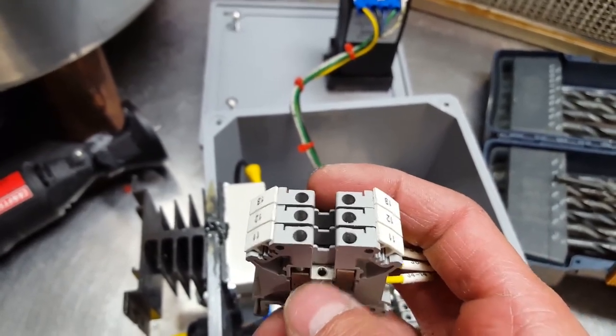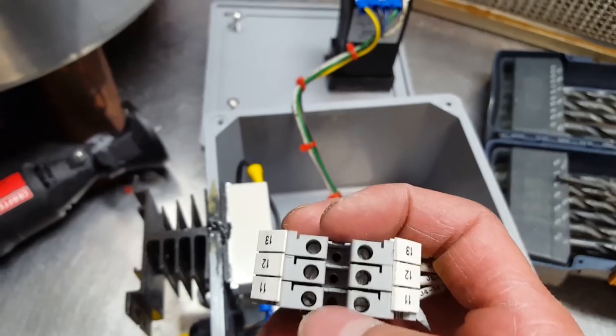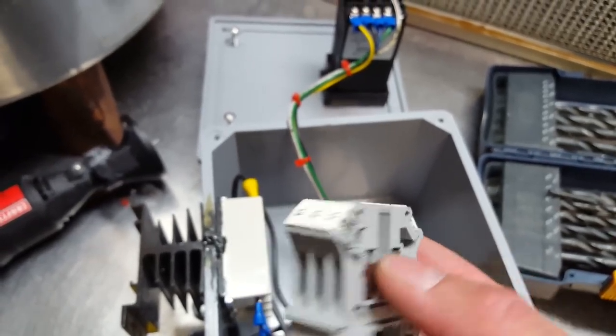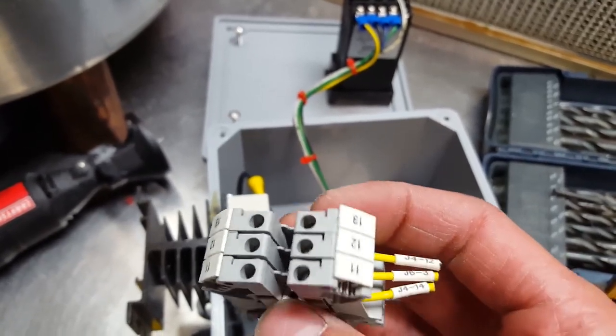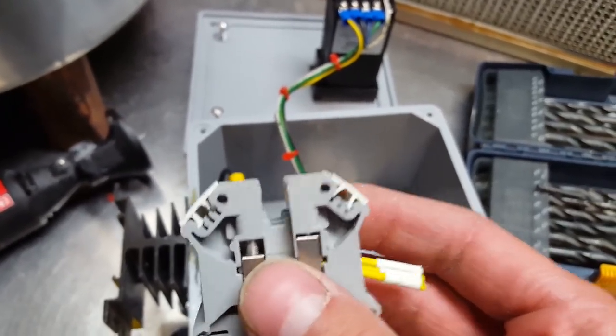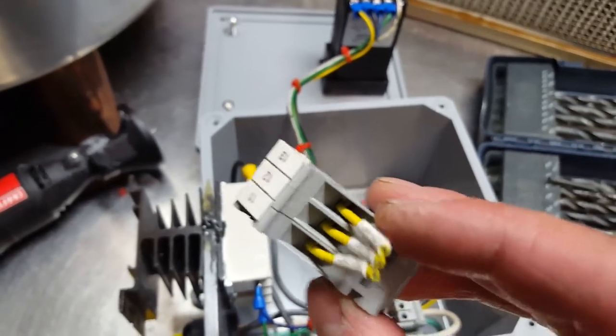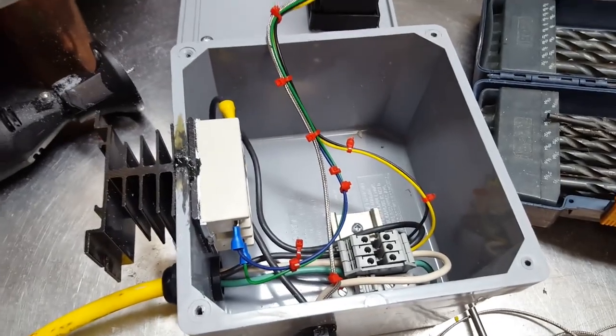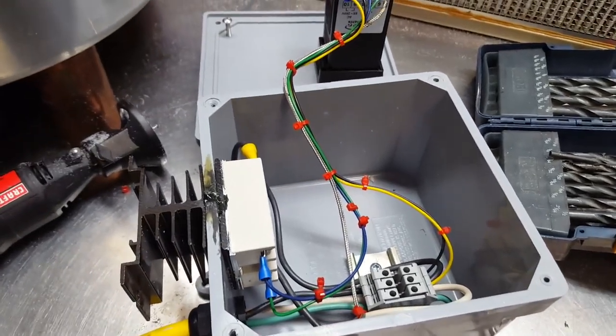You can also get jumpers that jump between circuits. Each one has a screw hole and you can use a jumper bar however many circuits you need. I think they usually go like five or ten circuits but you can trim them to size as needed. These make really clean installs, they're rated for 40 amps so should work pretty well.